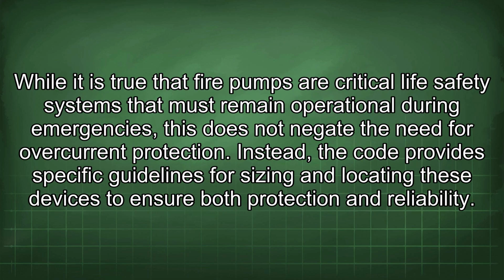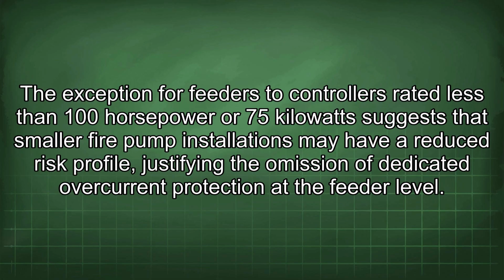While it is true that fire pumps are critical life safety systems that must remain operational during emergencies, this does not negate the need for overcurrent protection. Instead, the code provides specific guidelines for sizing and locating these devices to ensure both protection and reliability. The exception for feeders to controllers rated less than 100 horsepower or 75 kilowatts suggests that smaller fire pump installations may have a reduced risk profile, justifying the omission of dedicated overcurrent protection at the feeder level.